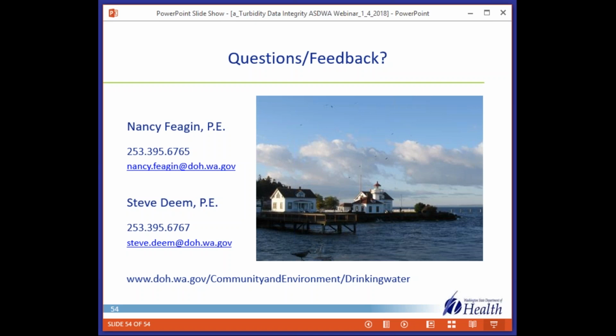Yeah. The next question, would you change any of your recommendations for raw surface water tap locations? Oh, skipping it, sorry. We found that setting the turbidity alarm at the highest range, 5 NTU, failed to set off the turbidity alarm as the alarm could not read above the analyzer. Have you come across a similar situation?